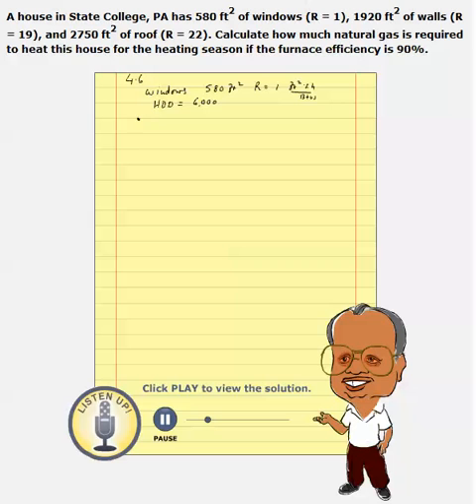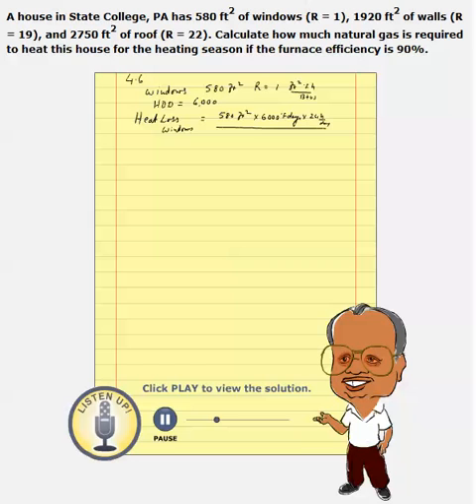We have all three parameters, so now heat loss through windows can be calculated using the formula: area times HDD times 24 hours per day divided by R value. That is 580 ft² × 6,000 °F·days × 24 hr/day ÷ 1. The units — ft², °F, hours, and days — cancel appropriately, and we are left with BTUs. In a season, we will be losing about 83,520,000 BTUs through windows.